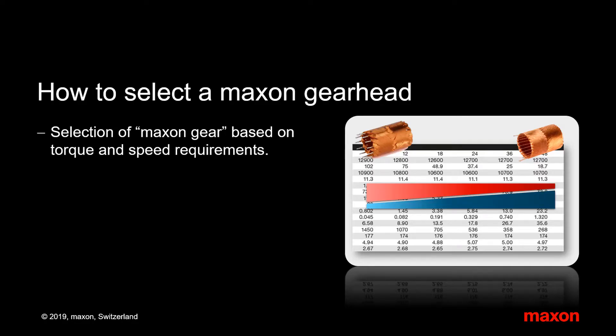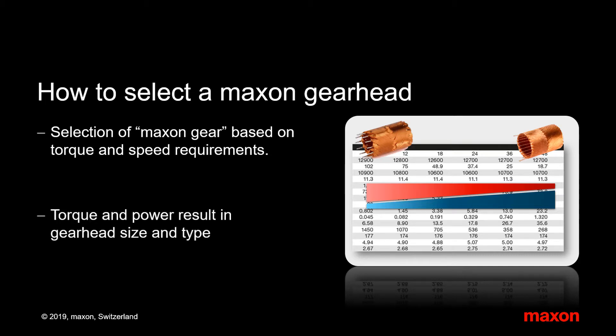That's it — a short introduction to gearhead selection. In summary: first select the gearhead size and type according to the torque requirements of your application. The matching reduction ratio is found by looking at the load speed and the maximum gearhead input speed.